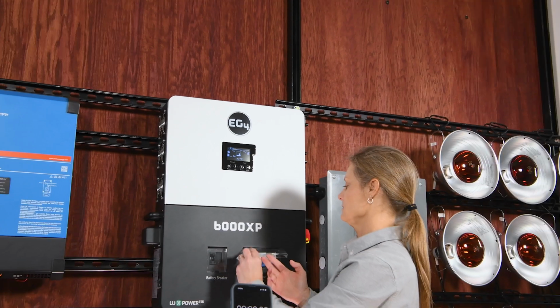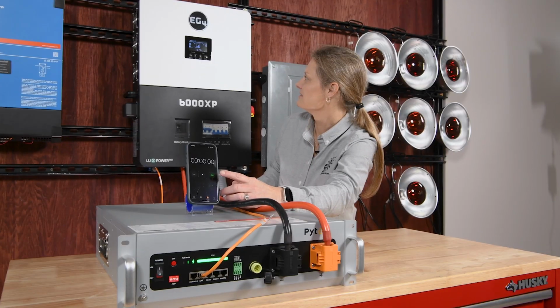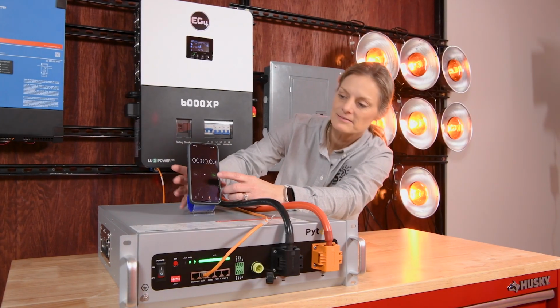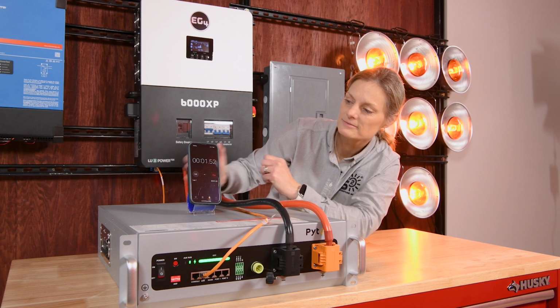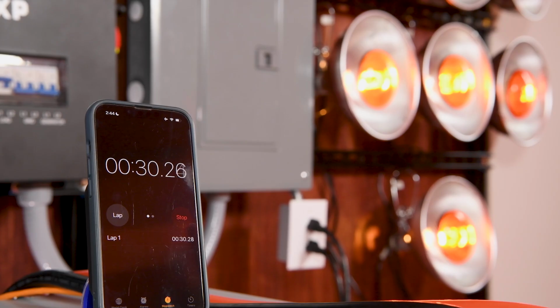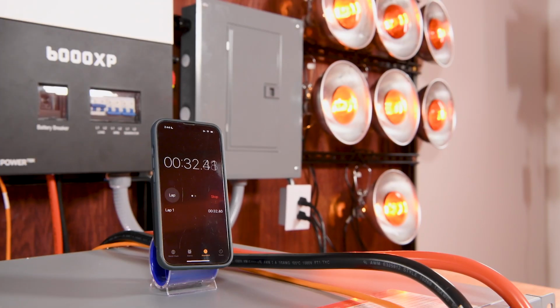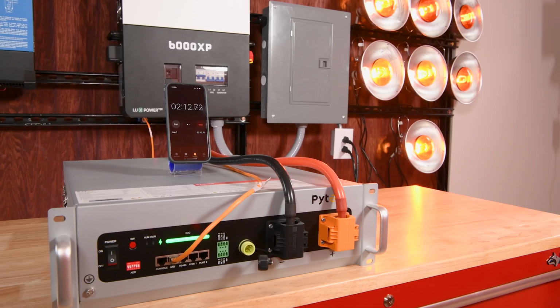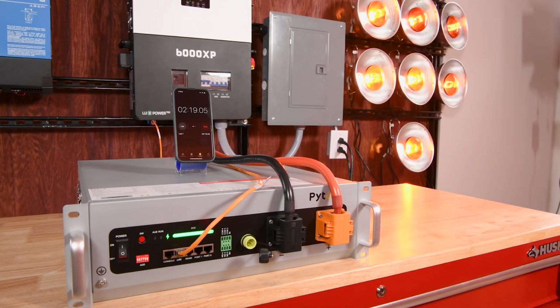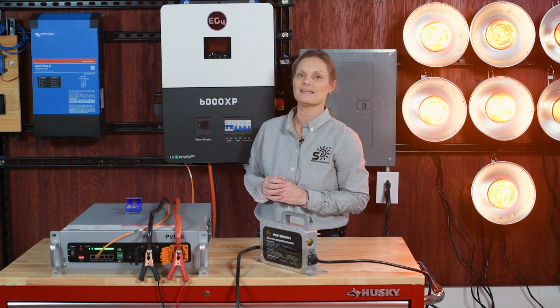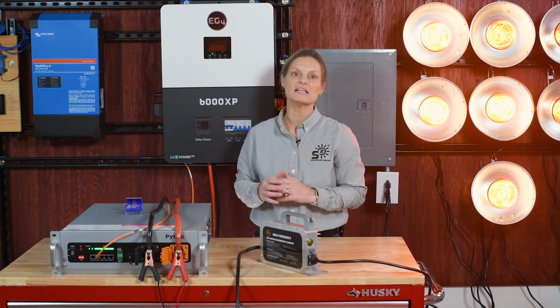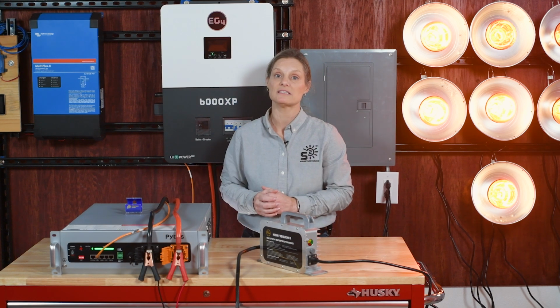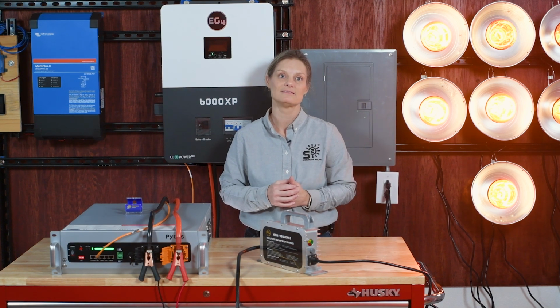Let's go ahead and run this test to see how long it actually takes to discharge the V5 with our current load once we fully charge it to 100%. We'll keep an eye on the time and come back once we reach the battery's limit. This test will give us a real-world measurement of how long the V5 can sustain a continuous load of 1.84 kilowatts, providing insight into its actual usable capacity under these conditions.